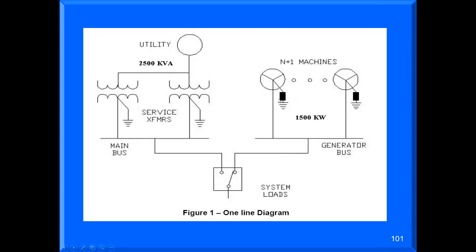The other way, if this was, say, a 400 amp system, and you don't want to go and change those settings, is I would design this so that anytime I see more than 400 amps of current, this has also got that protection. So just set the ground current where it sees 400 amps, and it shuts down on the solid grounded side. So that's your two options for that.